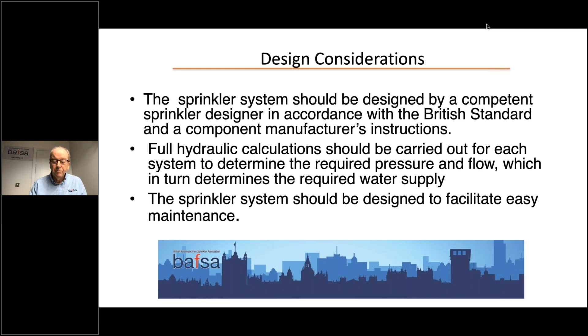The sprinkler system should be designed to facilitate easy maintenance. Too often we see systems installed, and then when they come to maintain them at a later date, they can't get access to the valves or valve groupings or other items that they require to service. So ensure it's designed to facilitate easy maintenance once the building is complete.